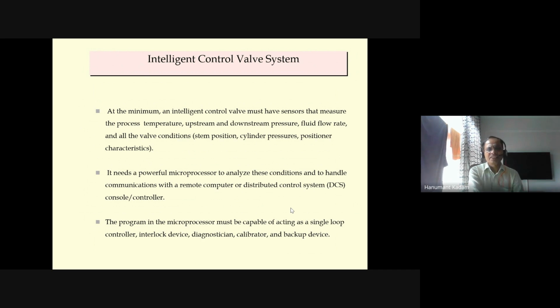Then it needs a powerful microprocessor to analyze these conditions and to handle communication with a remote computer or your host DCS system. This means the positioner has to communicate with the DCS, so it needs a microprocessor, the electronics you have seen in the block diagram. The program in the microprocessor, the algorithm developed in it, must be capable of acting as a single loop controller. This is very important.